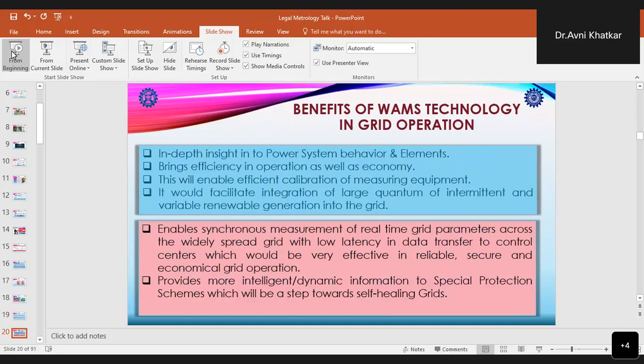Now, having this WAMS technology in the grid is very beneficial for grid operation because it provides in-depth insight into the power system behavior and elements. It brings efficiency in operation as well as in the economy, and it will also enable efficient calibration of all the measuring equipment. And it will also facilitate integration of a large quantum of intermittent and variable renewable generation into the grid. And this also enables synchronous measurement of real-time grid parameters across the widely spread grid with lower latency in data transfer to control centers, which would be very effective in reliable, secure, and economical grid operation.